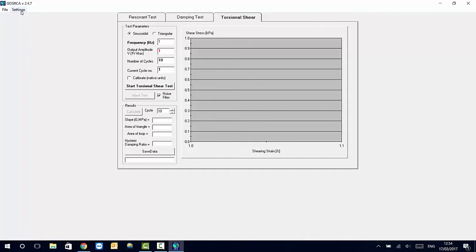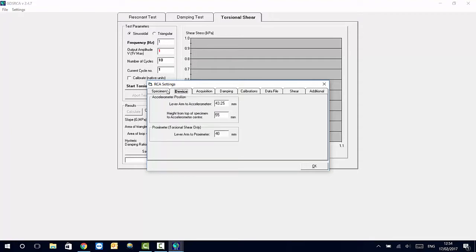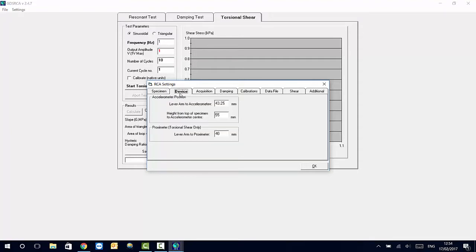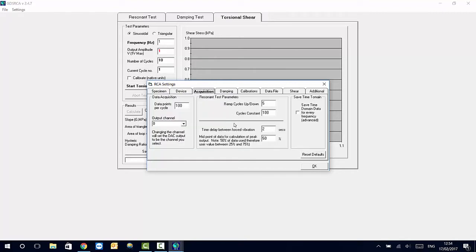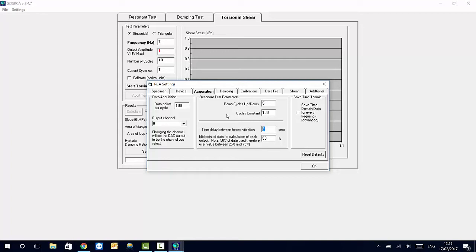How do we control the number of cycles that we run each one of these tests? Here, this is done from this setting, and here we can select things like the specimen details, the dimensions of the specimen. These are constants that are special for every machine that are used for the geometrical conversion from acceleration to a strain. For the excitation and the levels for strength of the system that the sample will achieve depending on the excitation mode that we have used for our test. And we can select the details of the acquisition system as in the number of cycles that we will run under a constant frequency for our test and the number of cycles up and down for the frequency to be achieved. And the amount of time that we will have in between every frequency increment.